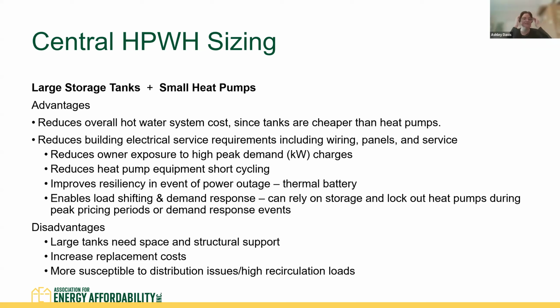There are some disadvantages to this, right? You might need really large tanks that are going to need more space and structural support than a typical design would. It can increase replacement costs. A 600-gallon tank is more expensive to replace than a 200-gallon tank, and it makes your plant more susceptible to distribution issues or really high recirculation loads. So designing that distribution system properly is going to be really important as well. Next slide.